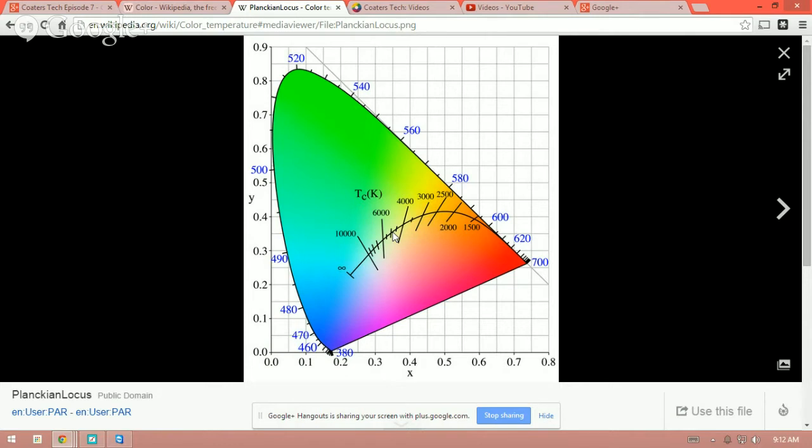So taking lenses out, stepping aside to a particular station or place where lighting is standardized is very, very important. Or you could change all the lighting in your entire lab to the exact same lighting, the exact same color. Either way is good. But light, color, and color temperature are very important in assessing color, especially in ophthalmics.